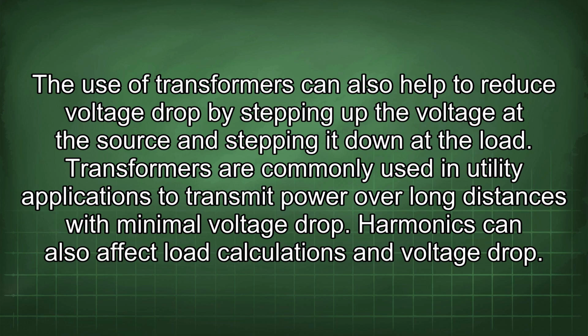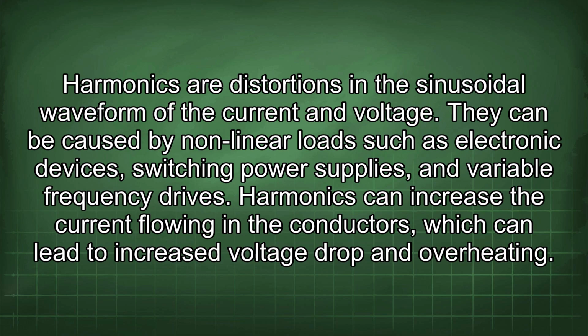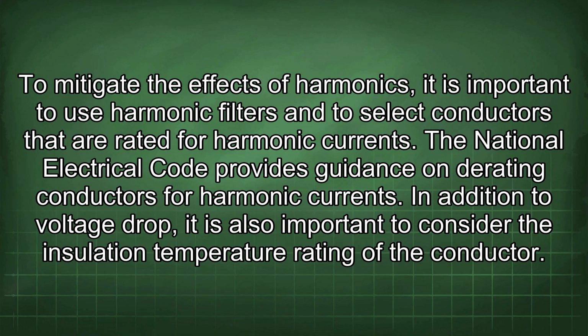Harmonics can also affect load calculations and voltage drop. Harmonics are distortions in the sinusoidal waveform of the current and voltage. They can be caused by nonlinear loads such as electronic devices, switching power supplies, and variable frequency drives. Harmonics can increase the current flowing in the conductors, which can lead to increased voltage drop and overheating. To mitigate the effects of harmonics, it is important to use harmonic filters and to select conductors that are rated for harmonic currents. The National Electrical Code provides guidance on derating conductors for harmonic currents.